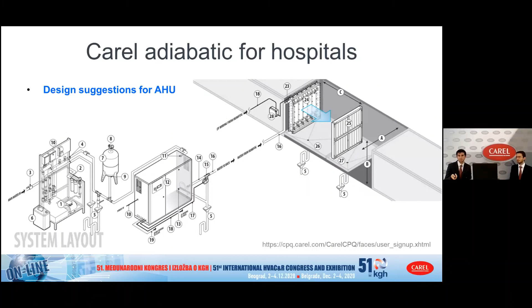Regarding this, we have to pay attention to some very important things. First of all, the installation of the drop separator, which must be installed with a slight slope to let the water drain better, and with frontal sealing, so it must be fully closed around the walls of the air handling unit to ensure the fog hits the drop separator and doesn't bypass it, because it is very dangerous to wet anything after the drop separator, like the filters.